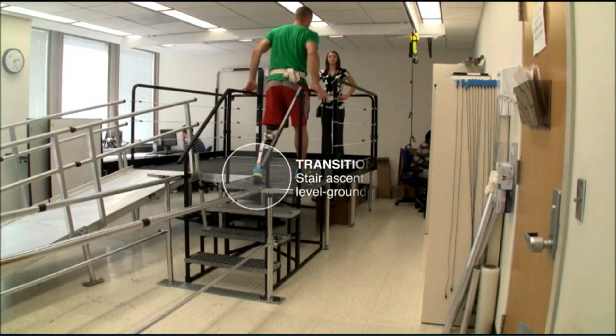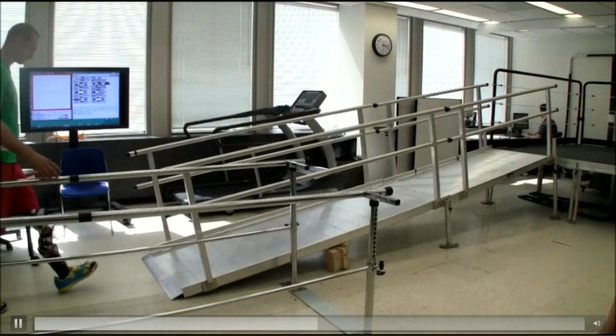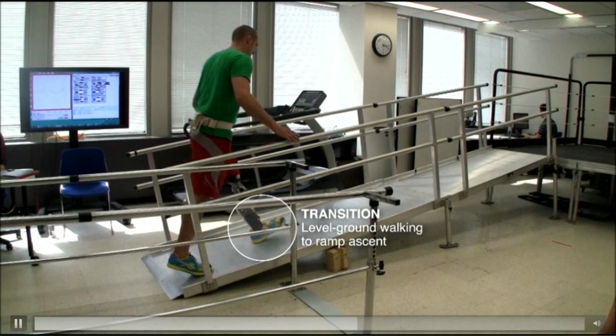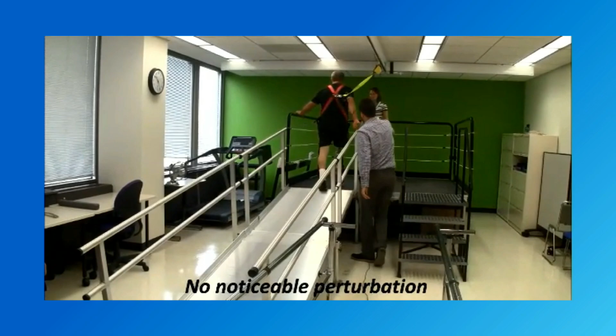Right? So we have to make these predictions so that we can swap in the best parameters. The spring needs to be a little more compliant, or the spring needs to be a little stiffer, or the equilibrium point needs to be adjusted. Same for walking up and down ramps and slopes and so forth. We do a pretty good job, but not perfect. Sometimes people don't notice if you make a wrong decision. The parameters for walking and walking up slopes are so similar that even though you swapped in the wrong parameter, the person doesn't really feel it. Quite often they feel it a little bit.